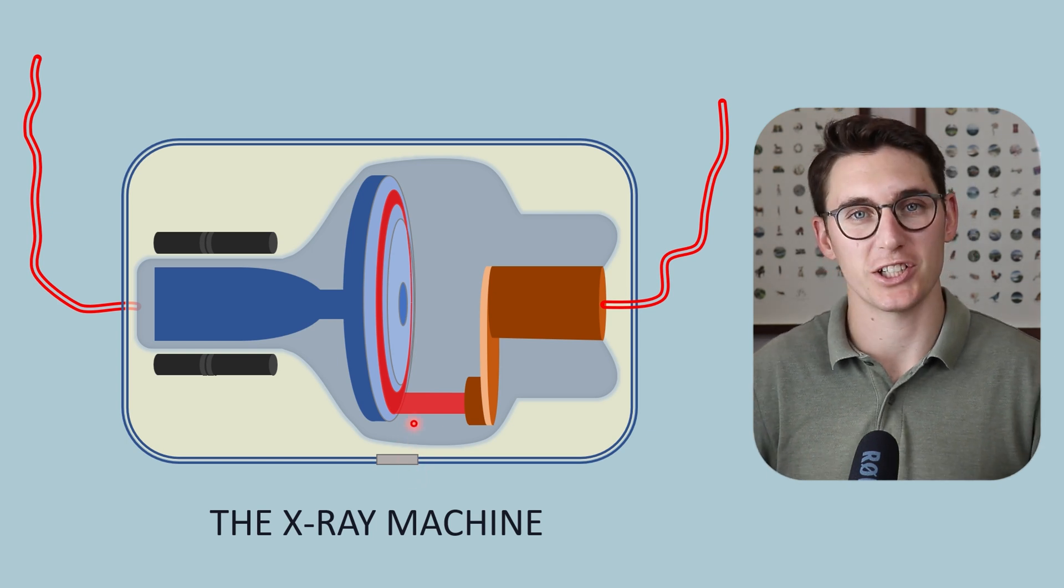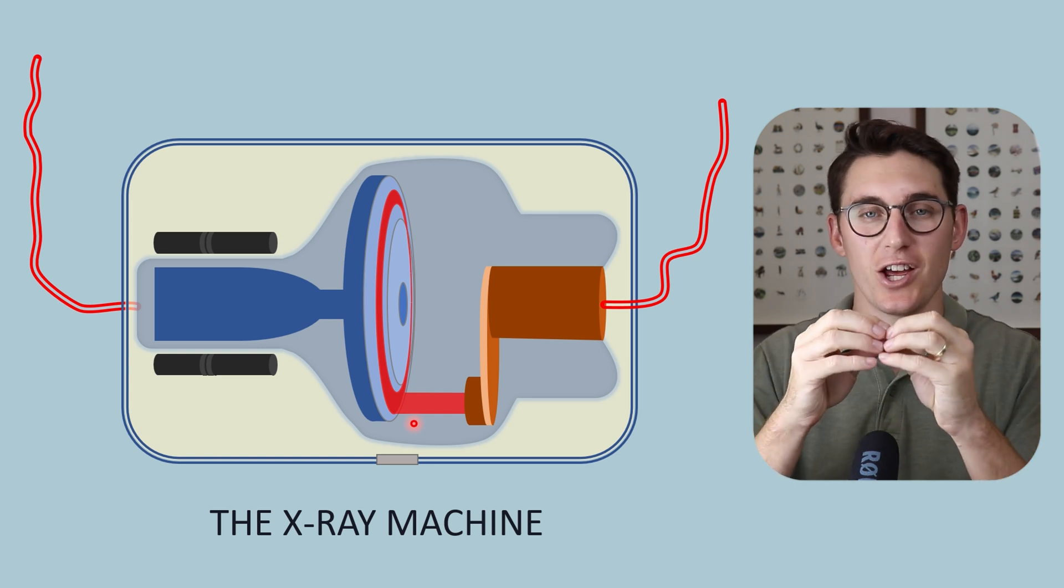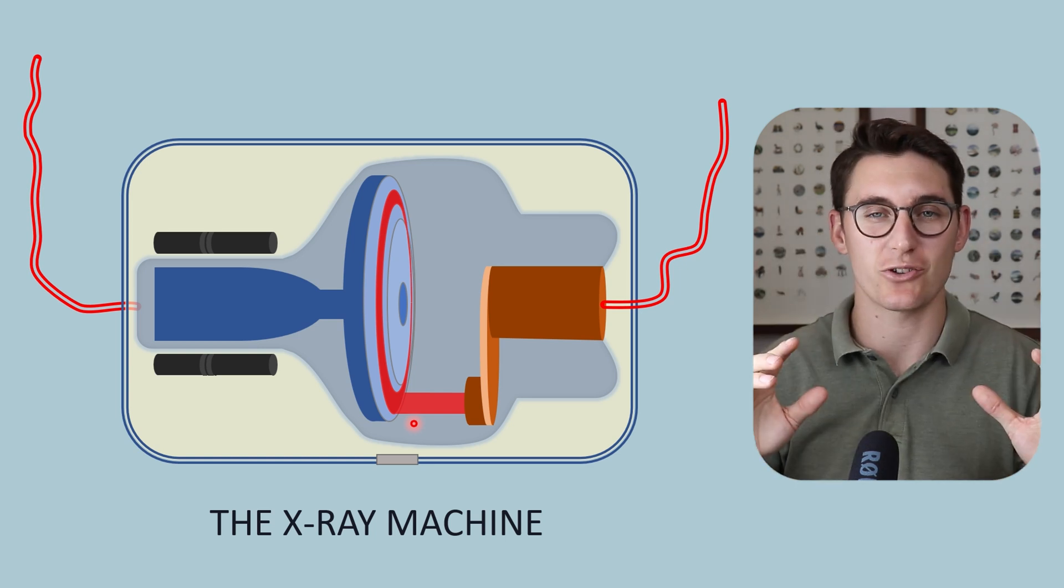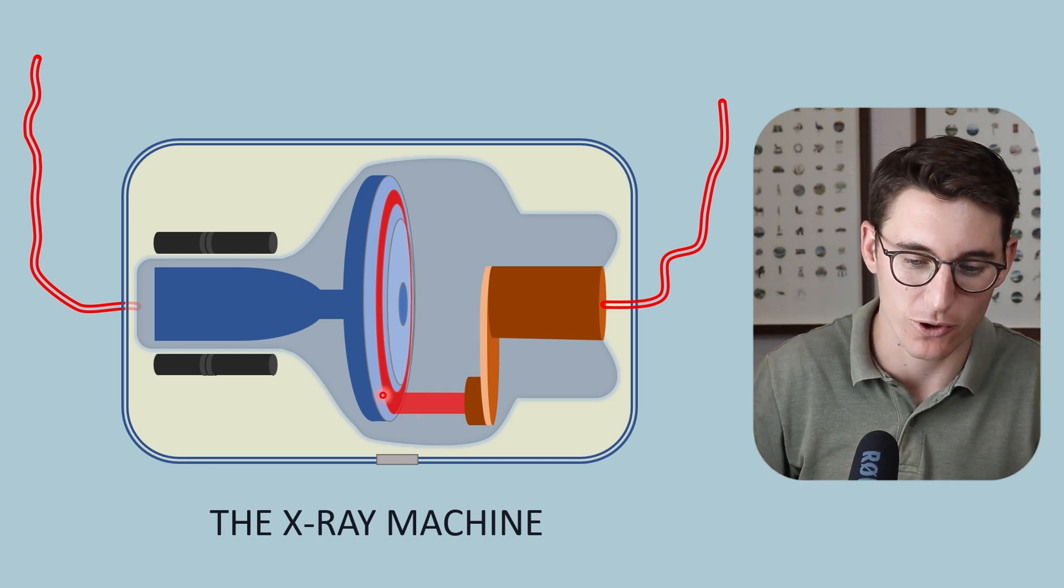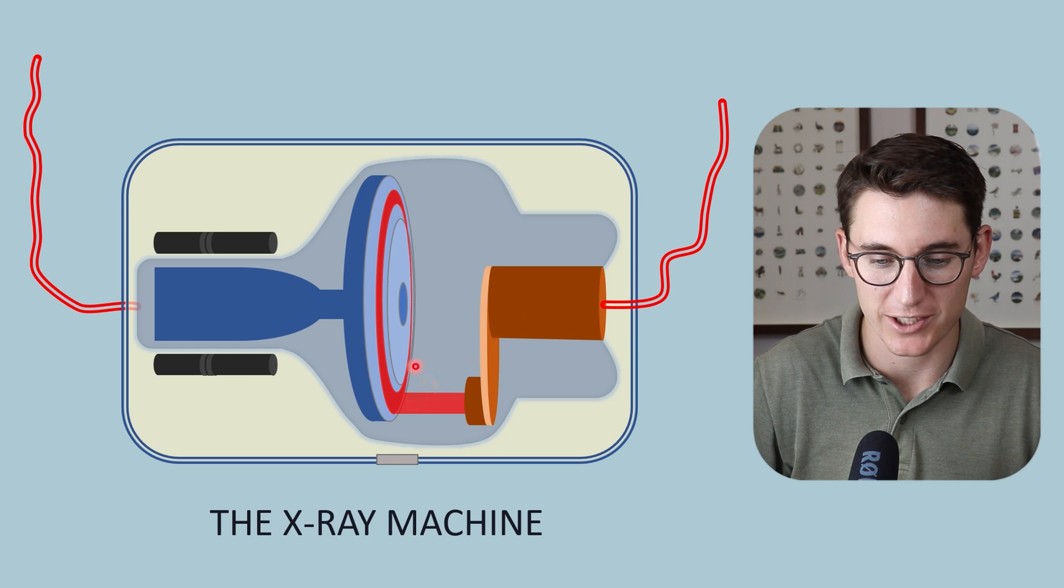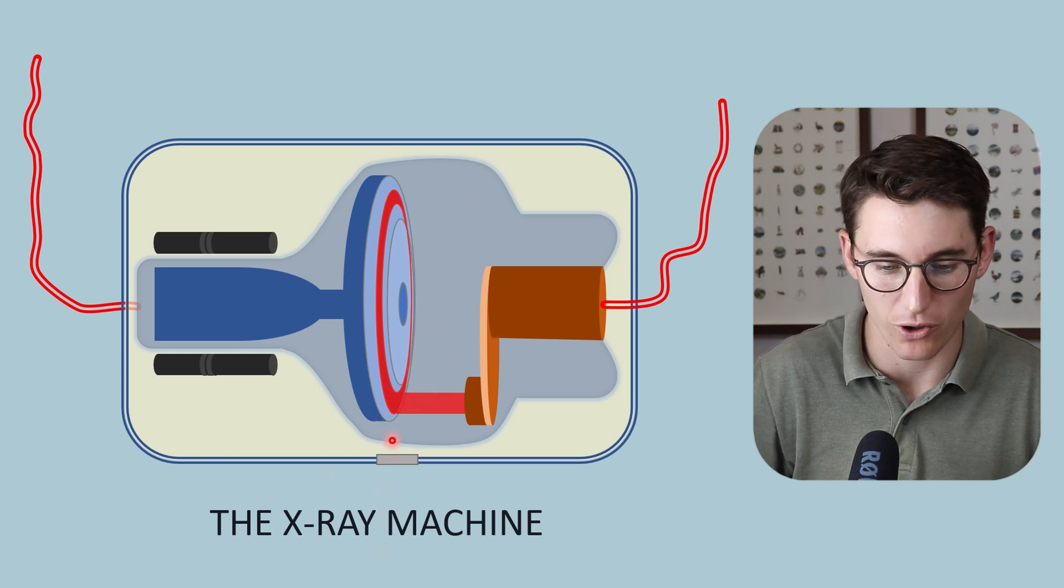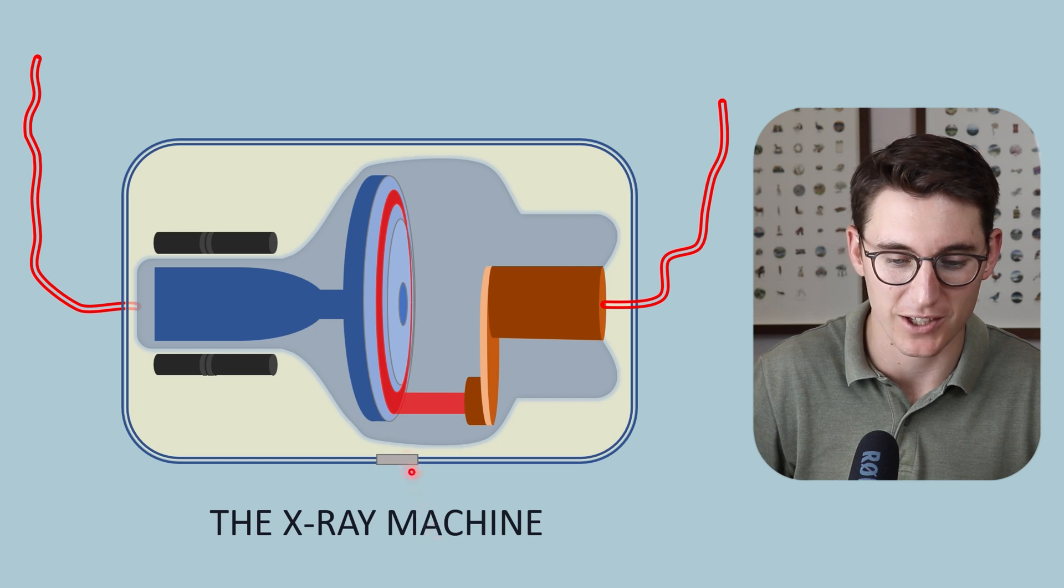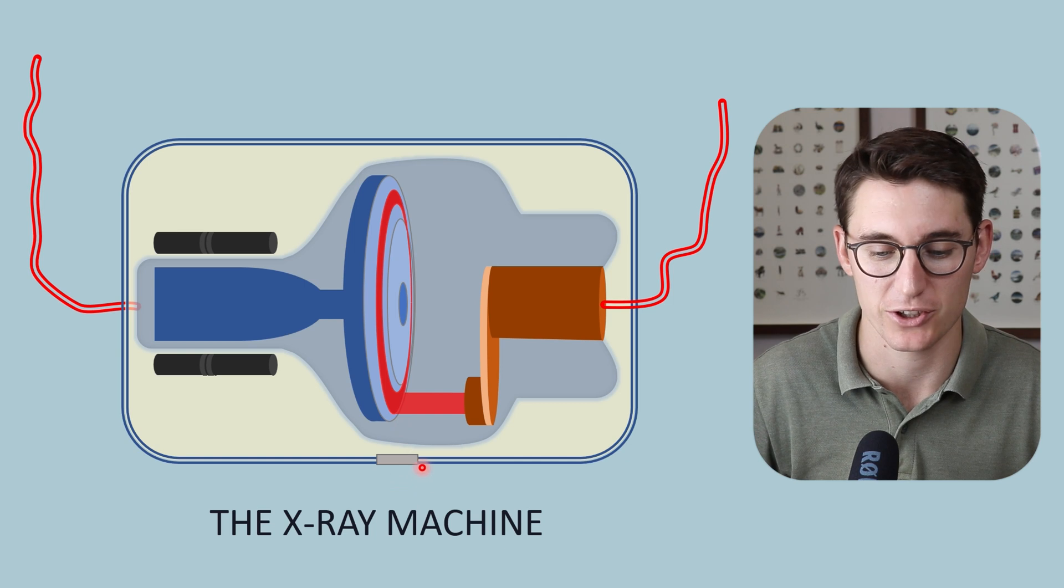Now x-ray production is what is known as isotropic. When we produce an x-ray within the anode, those x-rays can spread out in 360 degrees. There's no organized manner in which those x-rays are released from the anode. So x-rays can go in 360 degrees in all directions, and this window only allows this specific part of that isotropic x-ray release to be released towards our patient.